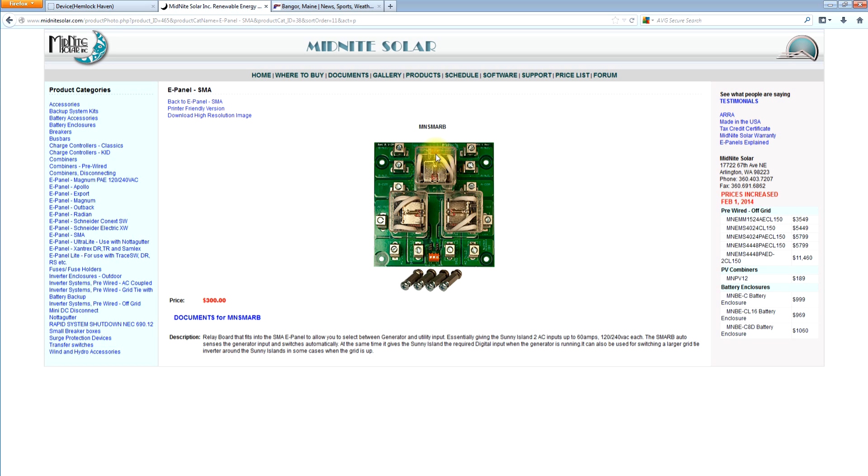And it can also give the SMA the digital input signal. It's hard to see, but right up above my mouse is an orange terminal block. And that's in there purposely, so that we can give the Sunny Island the digital input that it needs to know that it's now on generator and will not sell back to the generator.